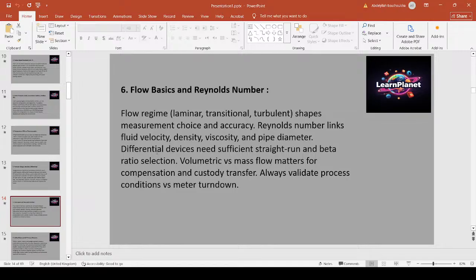Differential devices need sufficient straight run and beta ratio selection. Volumetric vs mass flow matters for compensation and custody transfer. Always validate process conditions vs meter turndown. Reynolds number indicates whether flow is laminar or turbulent. This determines which meters will perform well and what straight run is required for DP-based meters.